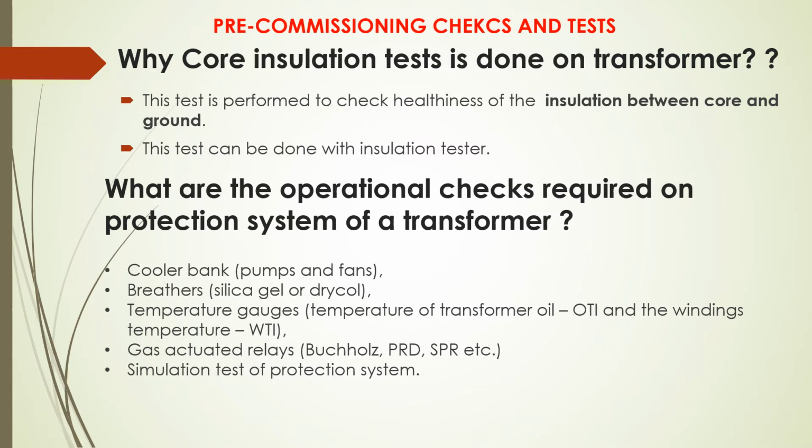What are the operational checks required on the protection system of a transformer? Cooler bank, pumps and fans, breathers, silica gel or drycol, temperature gauges, temperature of transformer oil OTI and winding temperature WTI, gas actuated relays, Buchholz, PRD, SPR, etc. Simulation test of the protection system.